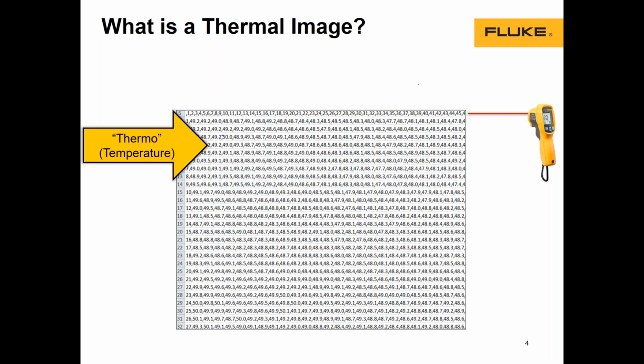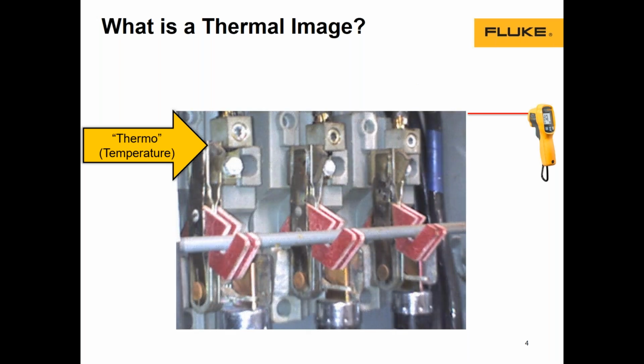If we want to have this with a thermal gun, we need to sample an entire area and collect all these measurements. While with a thermal camera, we'll have this in a single image, okay? And that is actually what the thermal camera sees. It's a large array of values, right? Now let's go to the image from the very beginning. What is the image that we're looking for? We're looking at an electrical panel image, right? And we're inspecting it, right?